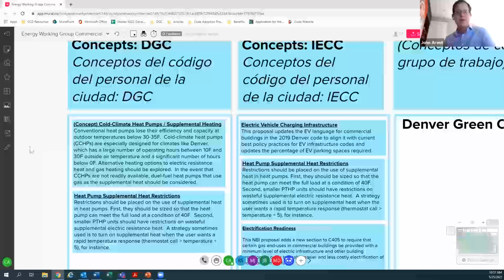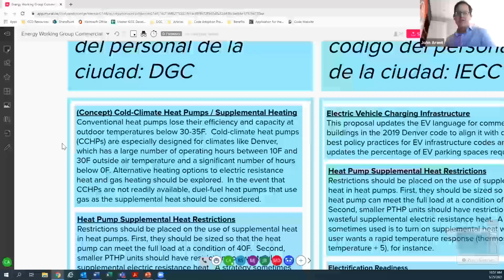cold climate heat pumps. This is an emerging technology. This would be more for the green code. Conventional heat pumps basically lose their efficiency at temperatures well below 30, 35, especially for buildings that operate 24/7, such as a multi-family mid-rise apartment building or other buildings that have early morning or evening hours. You're going to have a significant number of hours where the performance is compromised and where a traditional heat pump would use supplemental electric resistance heat, which is very inefficient.